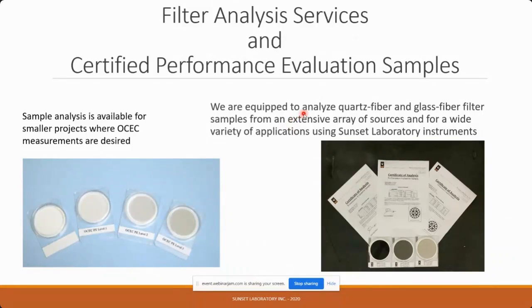Neither black carbon nor OCEC has an accepted standard, and this has to do with the chemical properties of EC and the fact that it's difficult, and we might say almost impossible at this point, to make a solution of EC or some other matrix to deposit EC on at a predictable, standardized concentration. We do, however, generate these performance filters, we call them, where we're able to collect a known amount of EC and OC onto a filter. We analyze them with our equipment and send them out to you for performance evaluation.